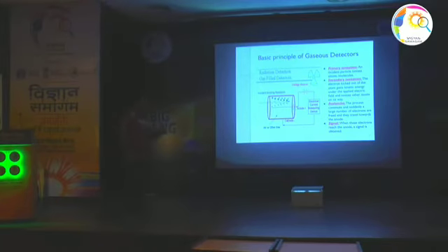If the electric field is strong enough, then those electrons will get enough kinetic energy to produce further electron-ion pairs, and that is called secondary ionization. And at the end, you will see one avalanche of electrons. Some electrons will be produced, and then finally I will collect those electrons by current or by some pulse, some external electronic circuit I need.